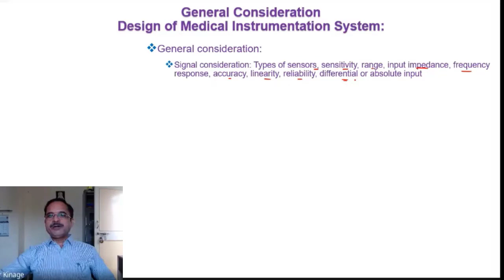Differential input means, in case of an instrumentation amplifier, it works on differential input - so whether you need differential or absolute input. Then there are environmental considerations like signal to noise ratio, whether it's able to work in a noisy area, stability, atmospheric temperature, pressure, humidity, vibrations, radiations, etc.